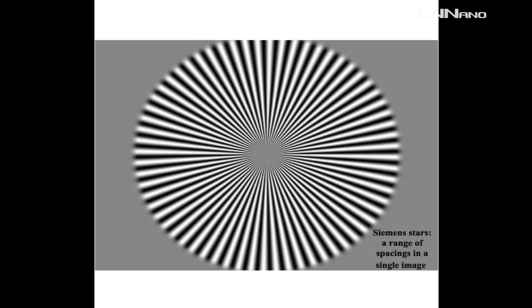And the way we tend to test optical systems is to look at objects like this that have a whole range of spacings. This is called the Siemens star, and it has a whole range of spacings in one single image. And you can see what the optical system is doing to your object directly. So in terms of our biological specimens, we would be interested in, say, 30 angstrom resolution out here, and as you go in here, you have 3 angstrom resolution at the inner part of this Siemens star. And the question then is, what does the electron microscope do to my images?